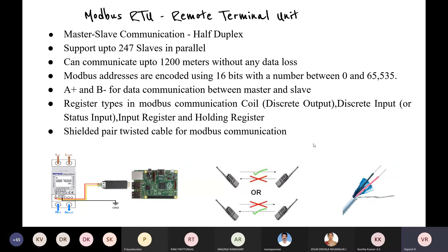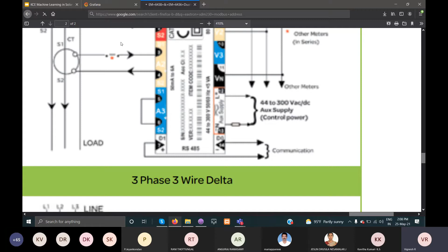I will show how to get the data for the Eastron meter. Just go to Google and type that particular meter and its model name with Modbus address. I recommend aggsoft.com. Here we can directly get the Modbus address as well as the Modbus description. You can see these are the Modbus offset values and these are the descriptions for those addresses. From that we can start receiving the data.